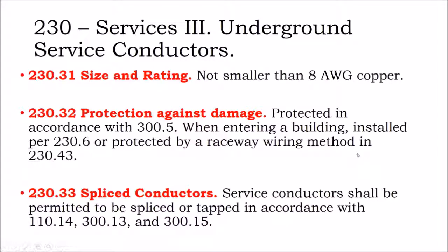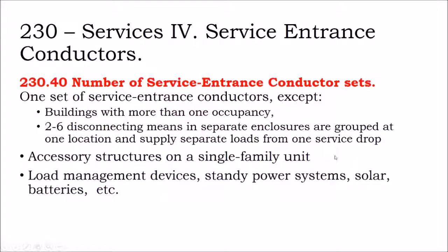Service conductors are permitted to be spliced and tapped, but only under certain conditions. So if you're inside an electrical box for a supply side tap, you are allowed to tap onto your service conductors. And how many service conductor sets can you have going into a building? As long as they are grouped together. If you have a special need to have more than one set of service entrance conductors, such as buildings with more than one occupancy, you can have 2 to 6 disconnecting means grouped together in one location from one service drop.